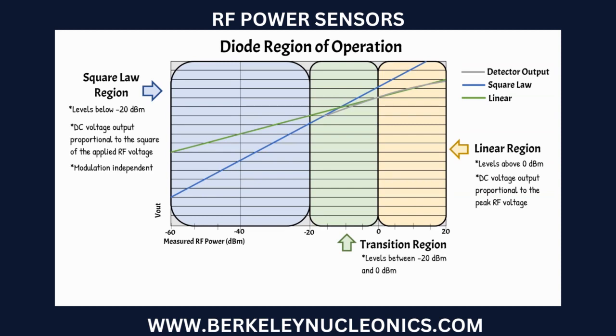The linear region is found at levels above 0 dBm, where the DC voltage output is proportional to the peak RF voltage. The transition region of a diode sensor is at levels between -20 dBm and 0 dBm. Diode behavior must be meticulously characterized within this region to produce accurate power measurements.